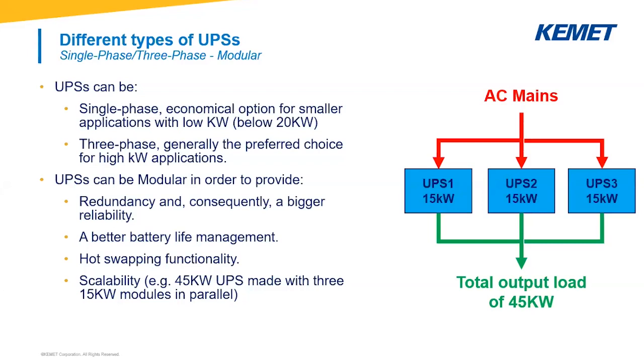Modularity in UPSs gives a lot of advantages. The first one is redundancy and consequently bigger reliability. A customer can decide to put an extra module that can be activated in case of a failure of one of the other modules, giving bigger availability of the UPS itself. Another important advantage is better battery life management, since the life of a battery is strongly dependent on the number of times it is charged and discharged. Having extra modules gives better management of these processes. Another function is hot-swapping — we can swap one module without turning off the UPS, without any risk for the final load.